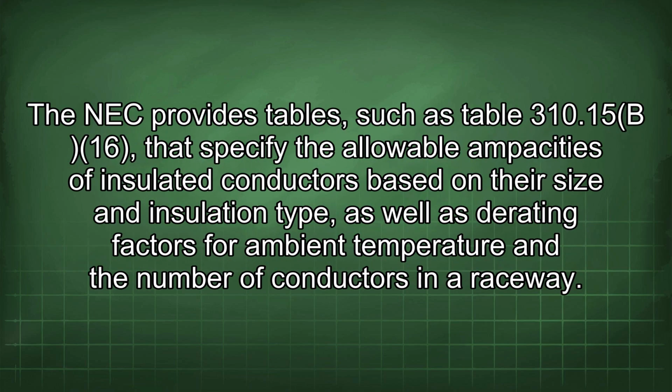The NEC provides tables, such as Table 310.15(B)(16), that specify the allowable ampacities of insulated conductors based on their size and insulation type, as well as derating factors for ambient temperature and the number of conductors in a raceway.